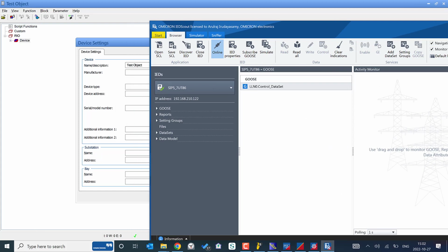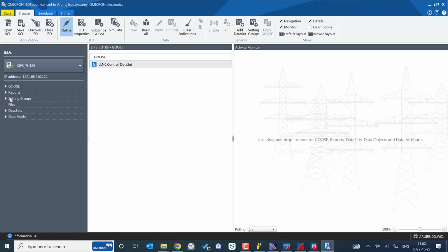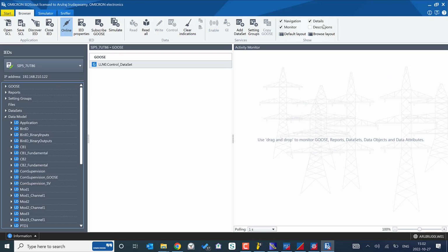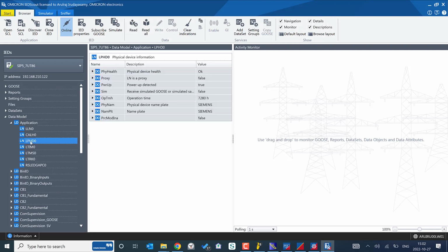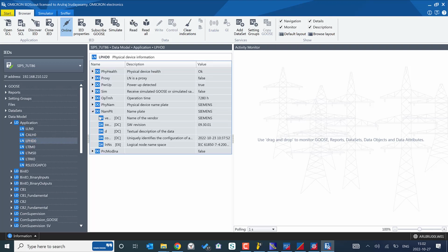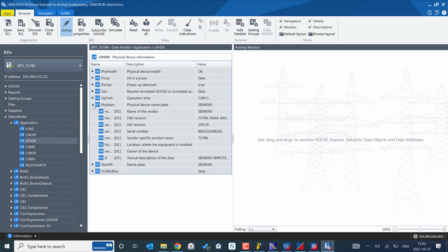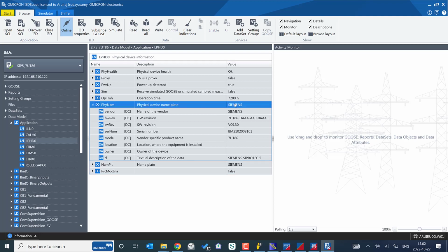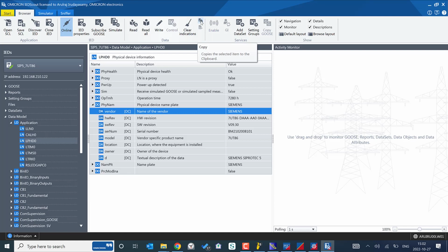So let's expand the data model. There you can enable the description to get many different pieces of information. Expand the application, select the LPHD logical node under the nameplate data object. In the physical name data object, you'll get much of the required information. For example, the manufacturer name or the vendor name is Siemens.